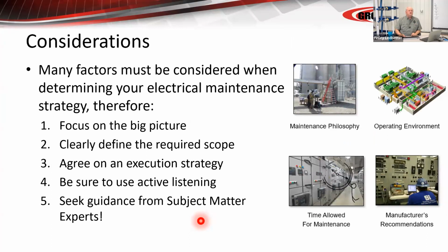There's many considerations. You know, there's maintenance philosophy. You've got to focus on the big picture. You've got to clearly design a scope for each section. We used to do a shutdown at Texas Instruments in Dallas where we'd bring in 150 people, 10 or 12 generators, 10 or 12 high current test sets, 10 Doble sets, and we'd test the entire site in a weekend. You don't see much of that anymore.